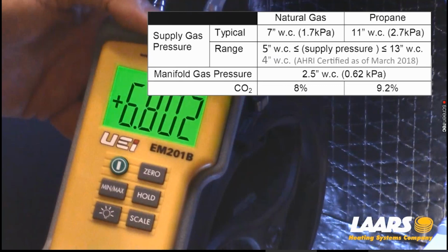So where are you? Now you're in ignition failure, and technicians were chasing the wrong problem, replacing igniters, dialing in CO2 2 or 3 times. Everything was fine, and it turned out to be the gas pressure under high demand was dropping below your rating plate. Okay?